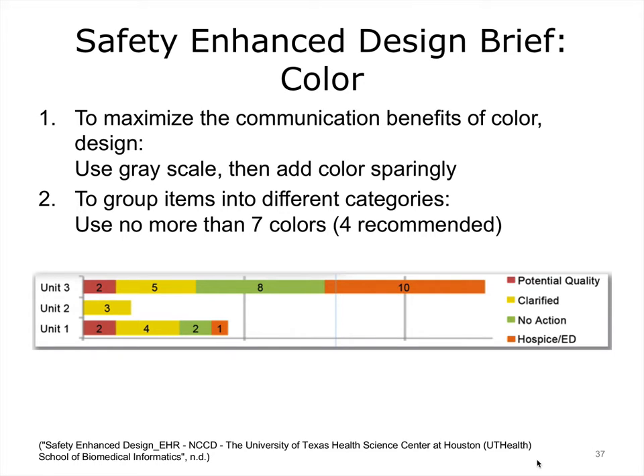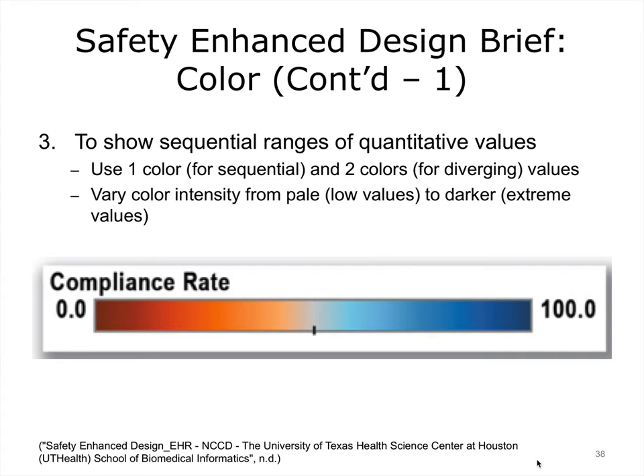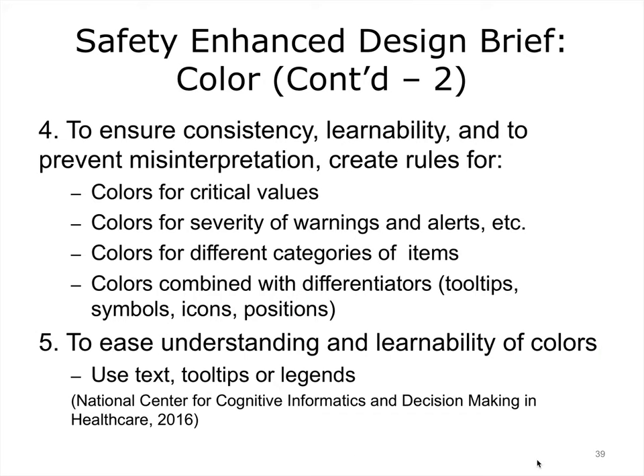To maximize the communication benefits of color design: use grayscale, then add color sparingly. To group items into different categories, use no more than seven colors — four recommended. To show sequential ranges of quantitative values, use one color for sequential and two colors for diverging values. Vary color intensity from pale for low values to darker for extreme values. To ensure consistency, learnability, and to prevent misinterpretation, create rules for colors for critical values, colors for severity of warnings and alerts, colors for different categories, and colors combined with differentiators such as tooltips, symbols, icons, and positions. To ease understanding and learnability, use text, tooltips, or a legend.